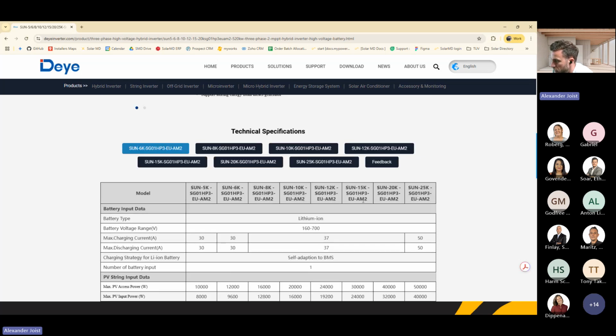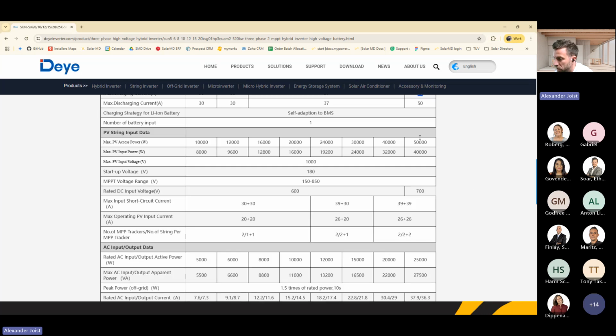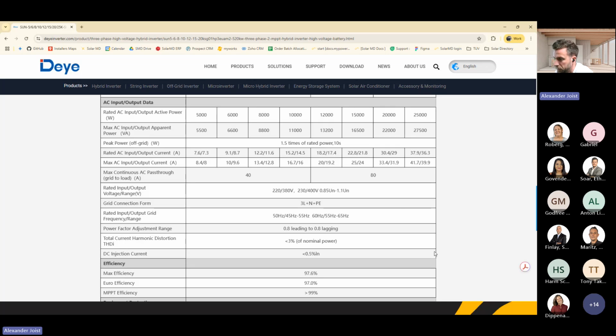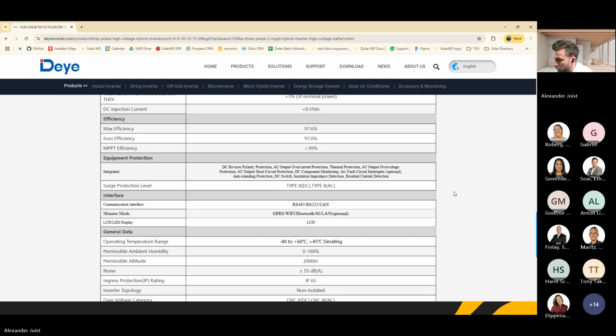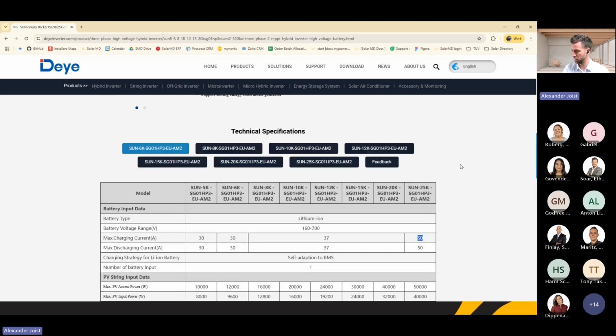The only thing we need to check now is the max charge and discharge current of this one, which is only 50 amps, quite low. So just need to be careful of that when using our batteries if you want the full output power of 25 kilowatts. But other than that, it should definitely work. From a compatibility perspective, it should work, we just need to note that it's only 50 amps.